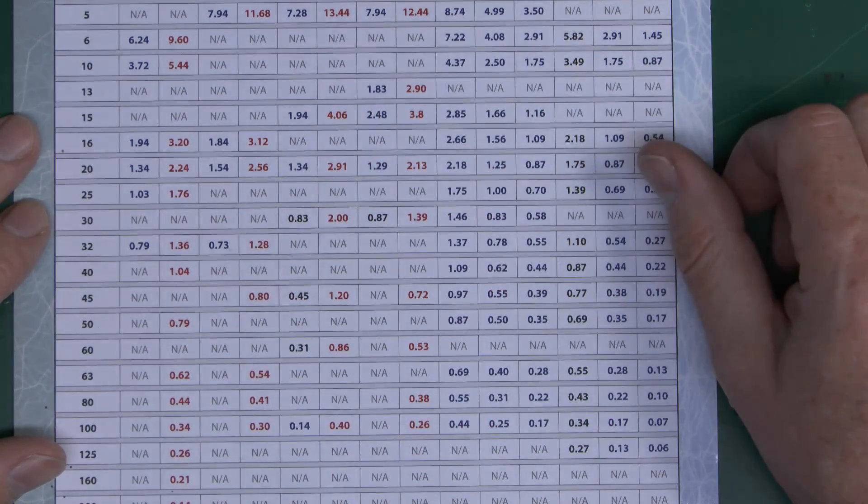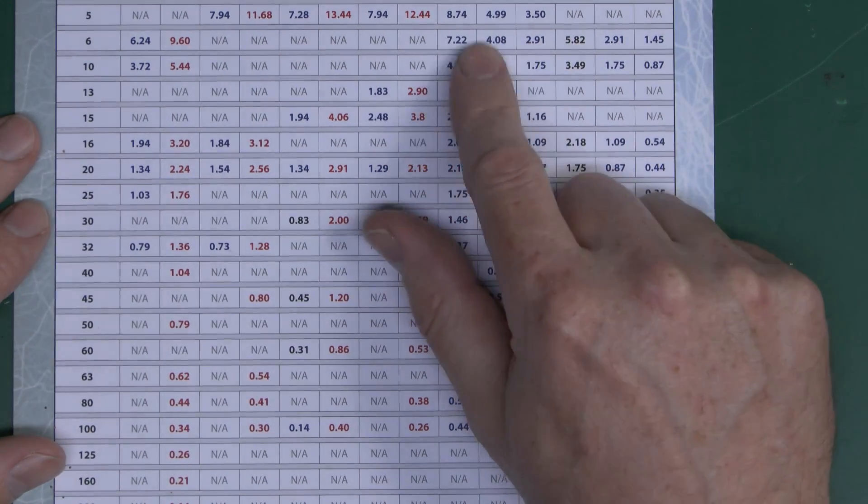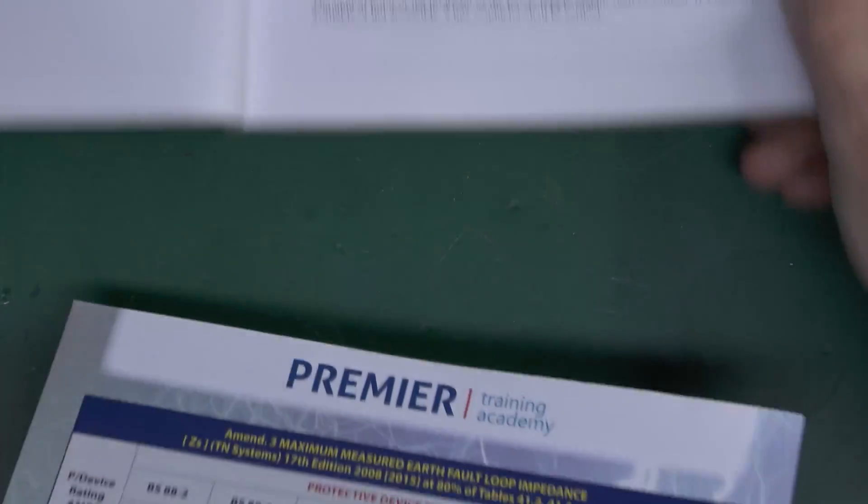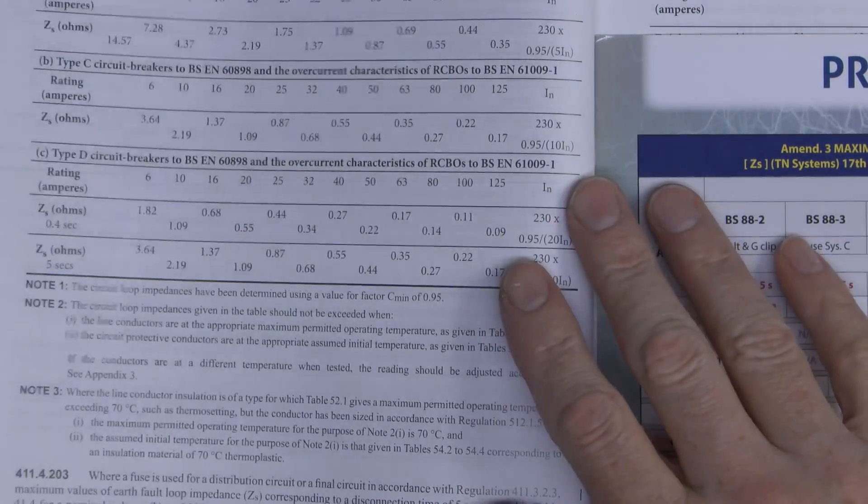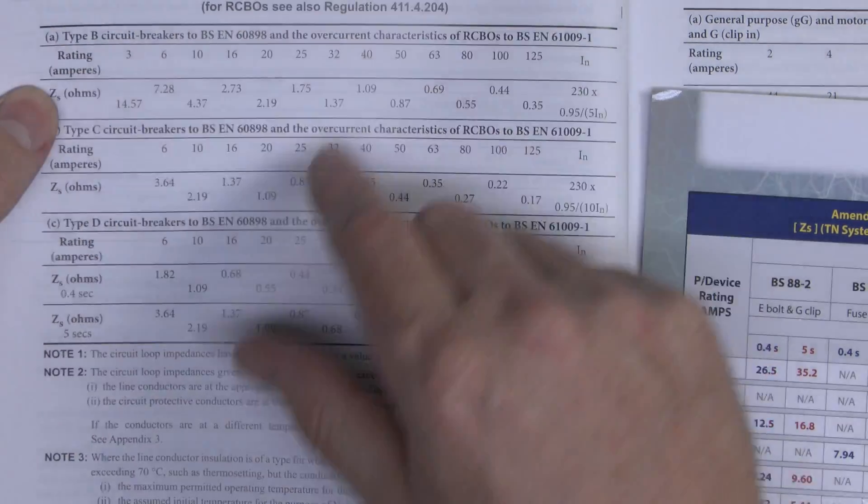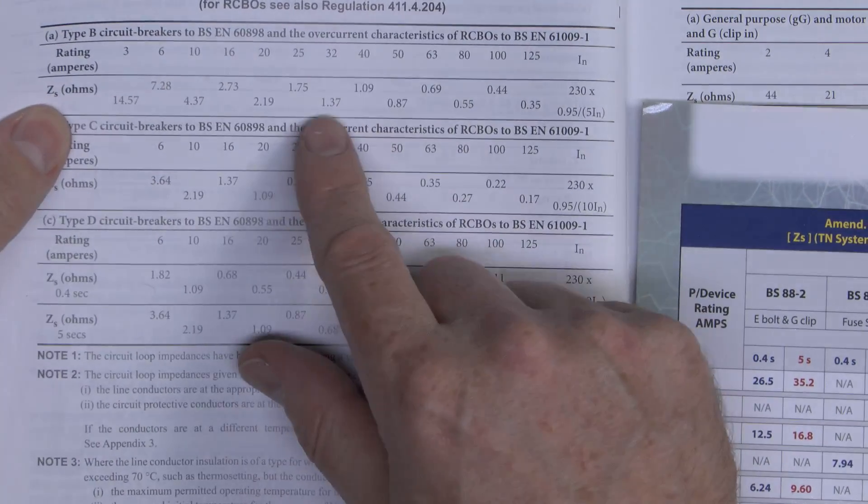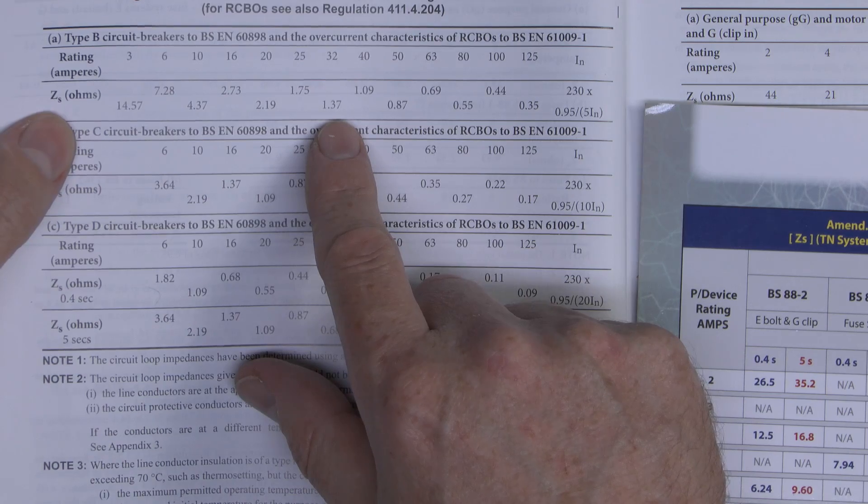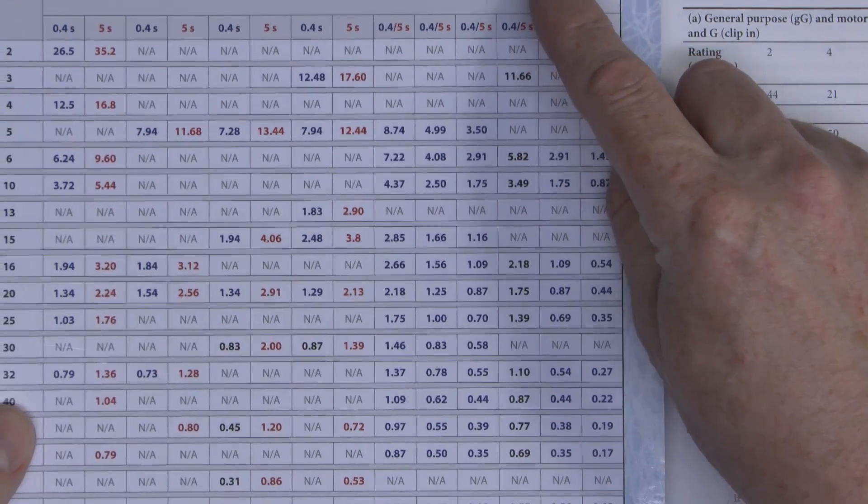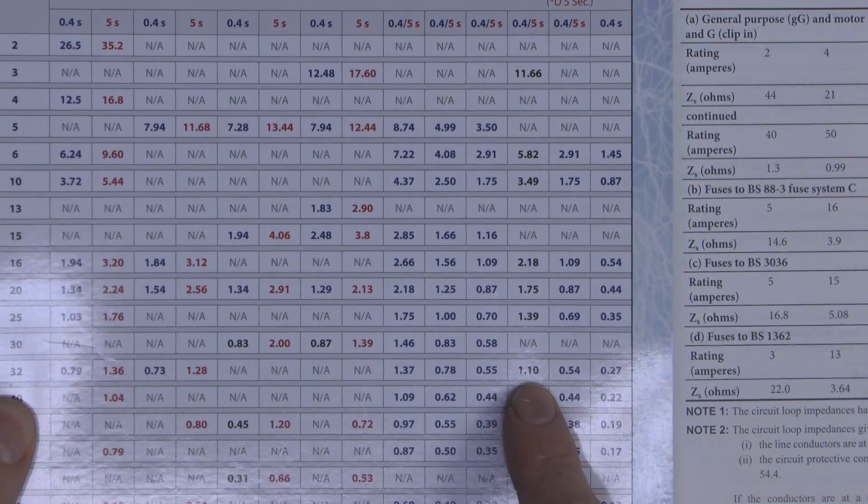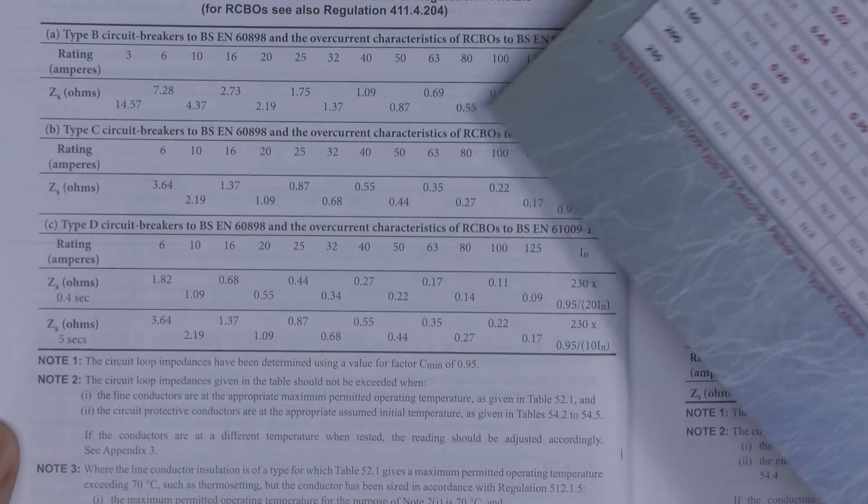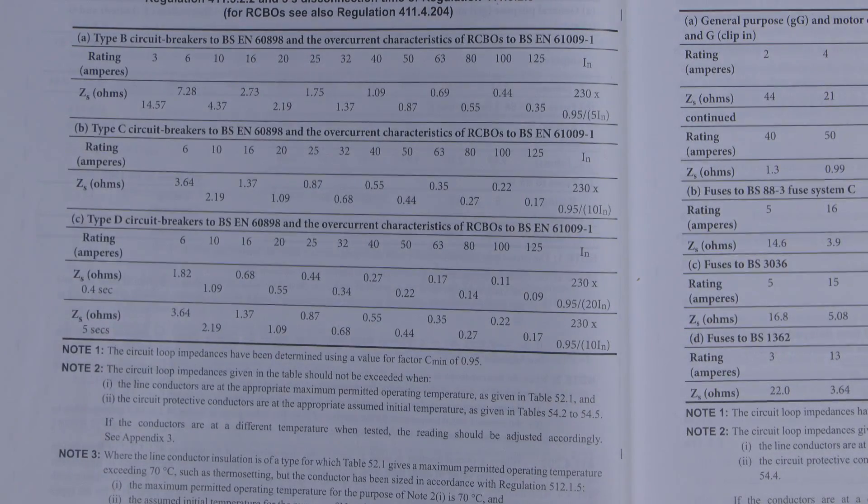So the question is then how are these values actually determined? And then the other question is why are the values in here different to the values in the book we saw previously? If we just have a look at one example, let's take a 32 amp circuit breaker, and it's going to be a type B. So type B and it's a 32 amp circuit breaker, and we can see the value here is 1.37 ohms. But if we look on this chart, and we have a look at type B circuit breakers and 32 amps, the value we're given is 1.10. So obviously there's some difference between 1.10 and 1.37, so we'll see how that works as well.